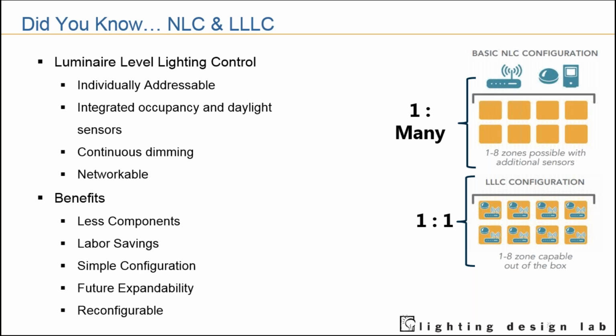You need to have both integrated occupancy and daylight sensors. You know how tough it is to commission daylighting according to code—you need a primary daylight zone, a secondary daylight zone, and to account for both vertical and horizontal daylight fenestrations. It's a lot of geometry to know where the daylight zones start and end. Just by having that integral daylight sensor, you don't necessarily need to do a lot of wiring calculations or geometry that the code requires.